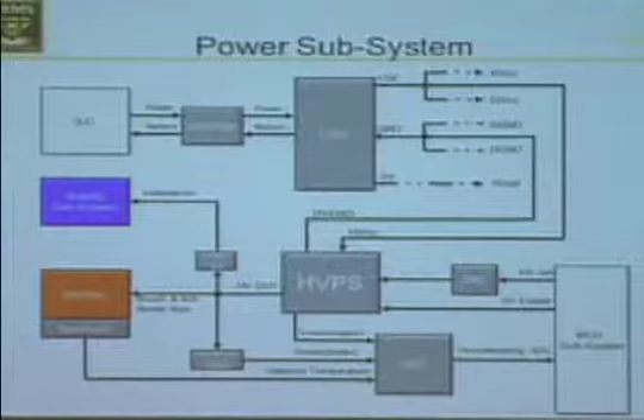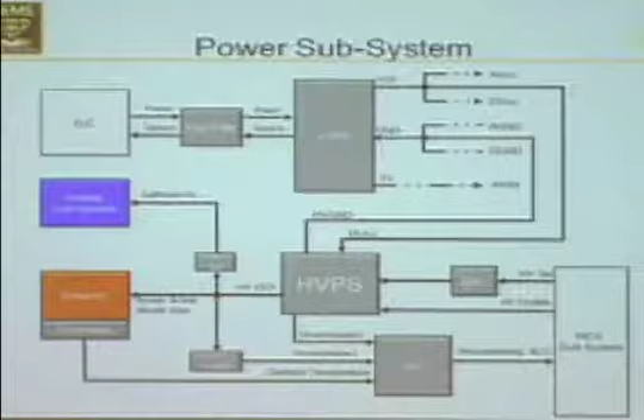In the same system, we have a high-voltage power supply. This is responsible for providing bias to the detector. One bias is provided directly, on the order of 2,000 volts. And then another bias is divided by 10 with resistors and fed through to the analog system. We also have some passive telemetry in the form of a thermistor on our detector to let us know what the temperature is. And then we've got 2 redundant monitors for the high voltage, as well as that detector temperature, and some basic control for the high voltage through a DAC.